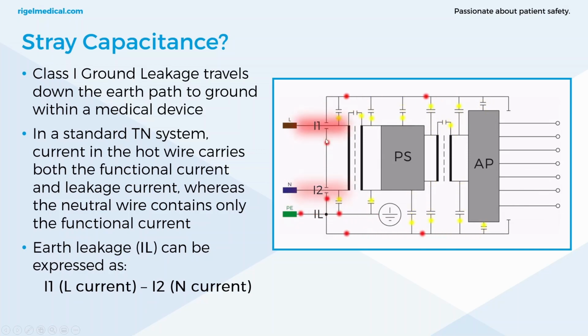So how does that work? From one of the first slides, we talked about how AC currents flow in a capacitor. The animation shows how capacitive currents flow to the enclosure from any internal components. In safe to use equipment, there is always a small leakage current flowing to earth. If the current's only a few microamps, then it's not hazardous. The earth connection is there to keep the user or patient safe in the event of a fault whereby substantial levels of current flow from the circuit occurs from the enclosure or the applied part. So it allows that current to flow down the earth path and not through the patient.